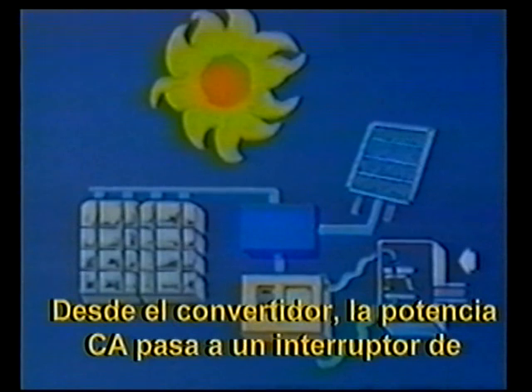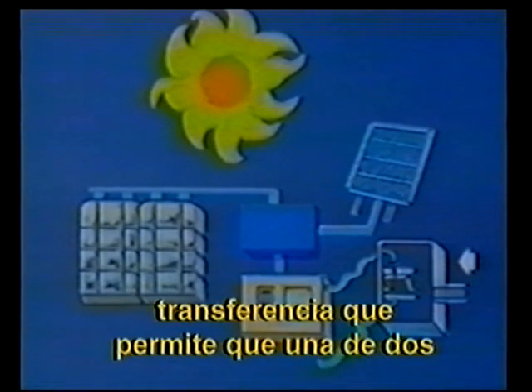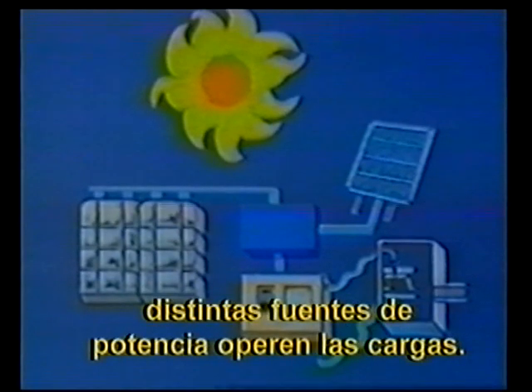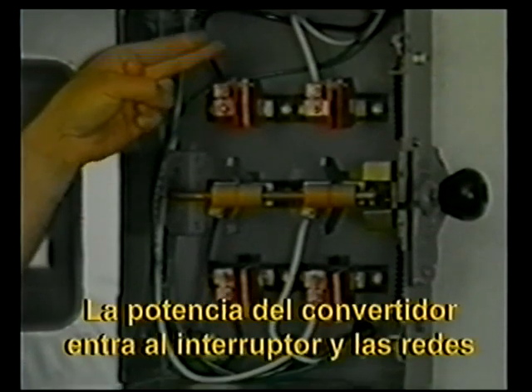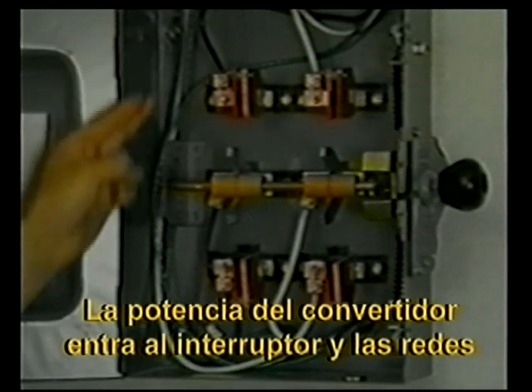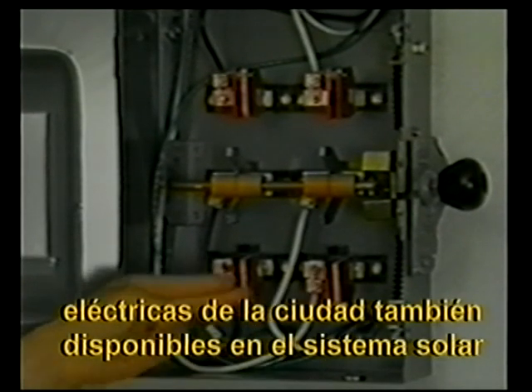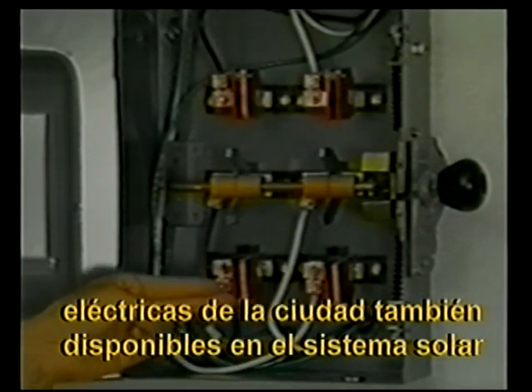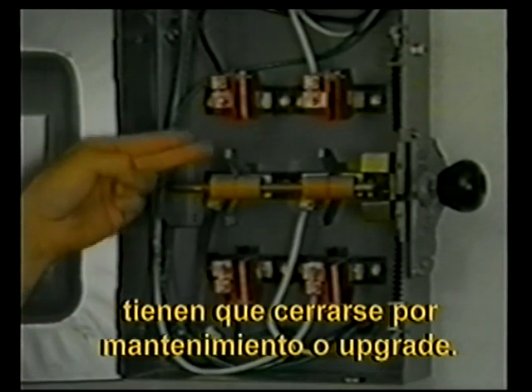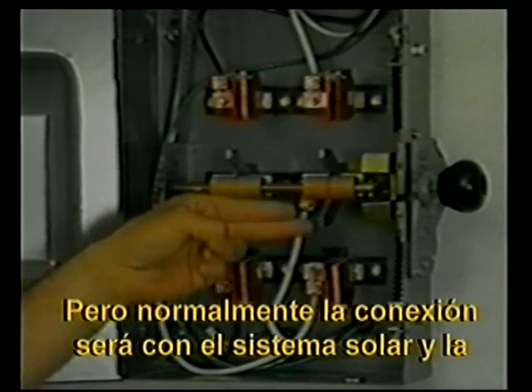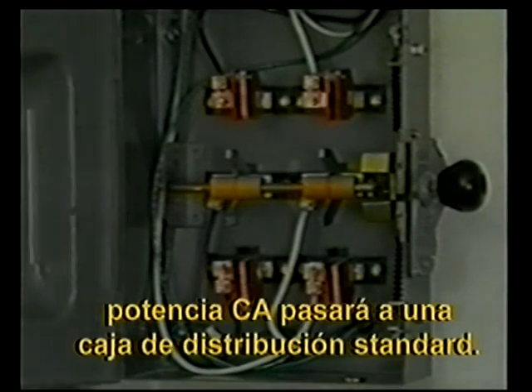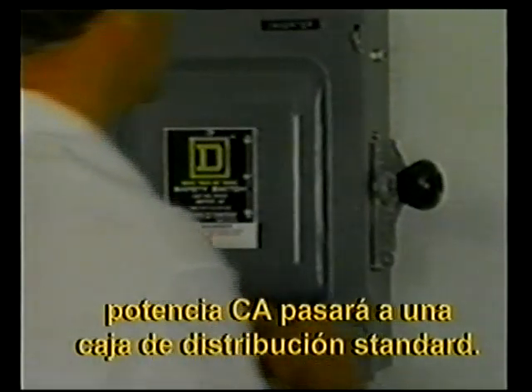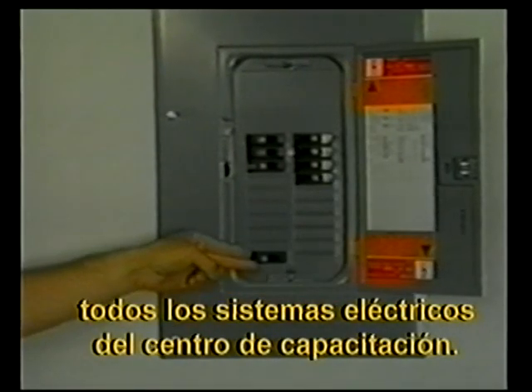From the inverter, AC power is passed to a transfer switch that allows one of two different power sources to run the loads. Power from the inverter comes into the switch, and city utility power is also available if the solar system needs to be shut down for maintenance or upgrading. But normally the connection will be to the solar system, and AC power will pass on to a standard distribution box. Here, standard AC circuit breakers protect all the training center's electrical systems.